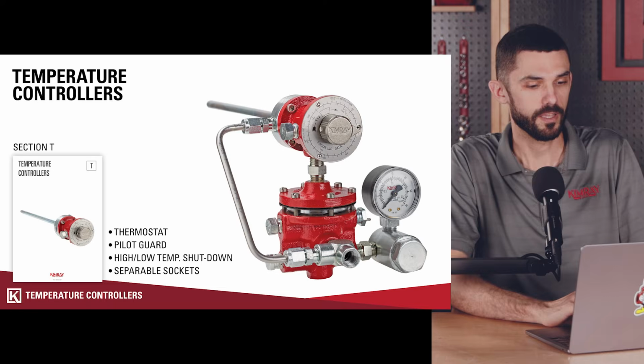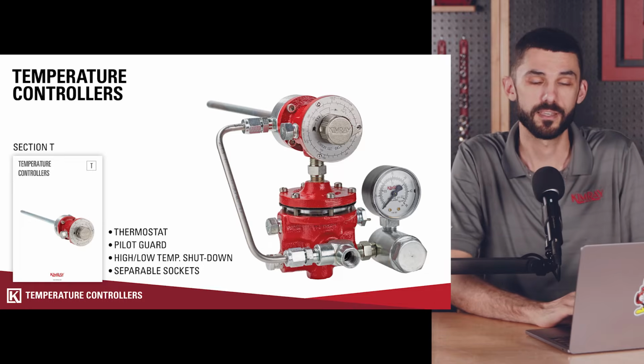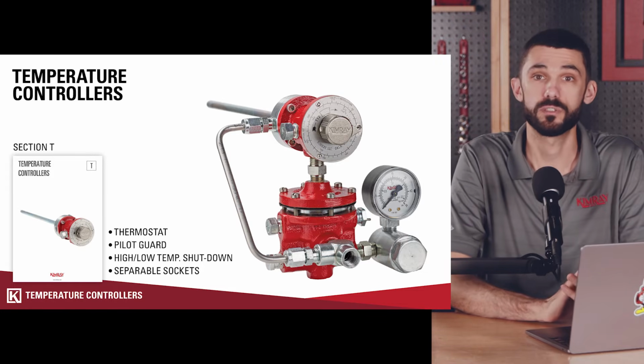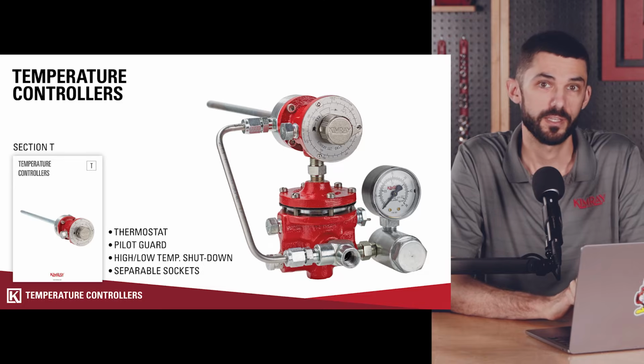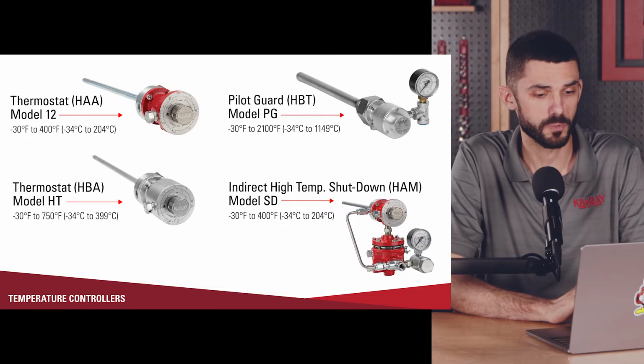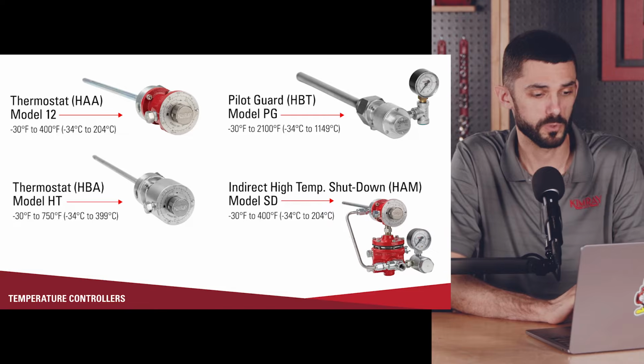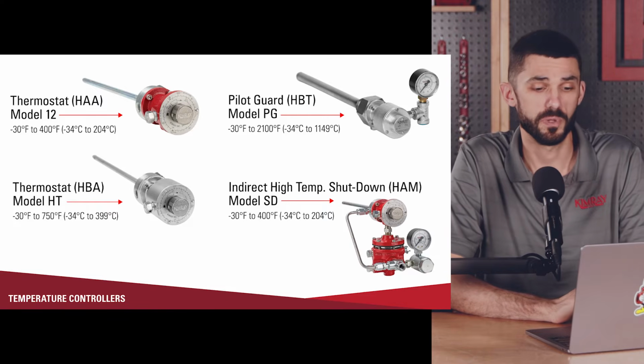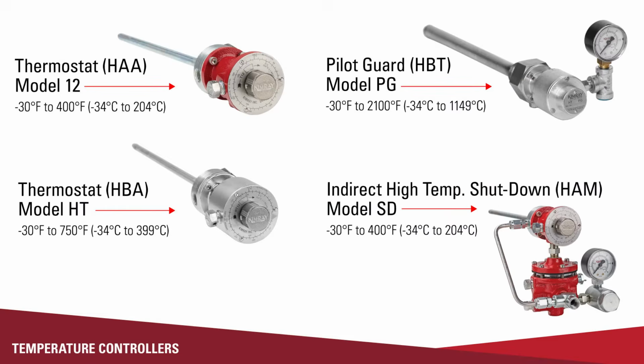All right, let's go ahead and get started with section T of our catalog. So thermostats control temperature of different processes. There's a couple of different options with the models within section T, but they control anywhere from -30 all the way up to 750 degrees Fahrenheit. That is their temperature operating range. I would say the majority of the processes in oil and gas are not going to be outside of that range.